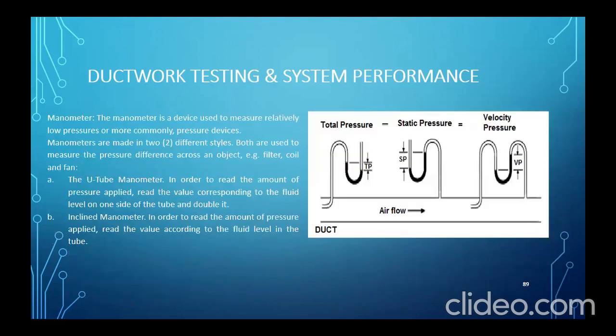So, manometer. Yan. The manometer is a device used to measure relatively low pressure, or commonly pressure differences. Manometers are made in two different styles. Both are used to measure the pressure difference across an object, that is, filter, coil, and fan. So yeah. Total pressure minus static pressure is the velocity pressure. Static pressure, total pressure dito. Yan, makukuha mo yan. So, airflow, pag dito ka nagkabit, static pressure. So, pag ito na ang ginamit mo, lalabas is velocity pressure. Okay?